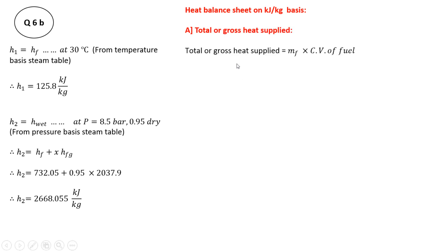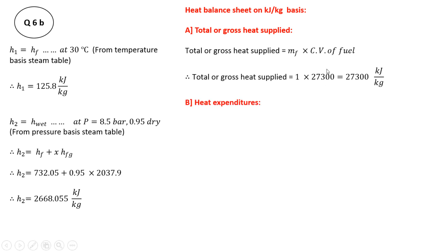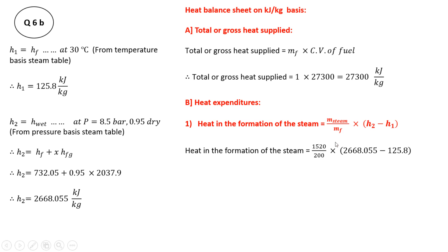The first part of the heat balance sheet is the total or gross heat supplied, which is mass of fuel × calorific value. On a per kg basis, mass of fuel = 1 kg, so gross heat supplied = 1 × 27300 = 27300 kJ/kg. Out of this, some heat is used in steam formation. The heat in steam formation = (mass of steam / mass of fuel) × (h2 − h1). Substituting the values, heat in steam formation comes out to be 19321.138 kJ/kg.